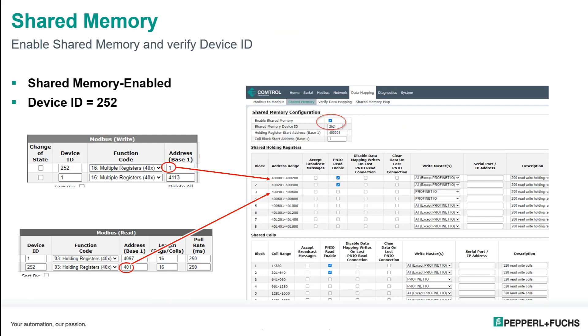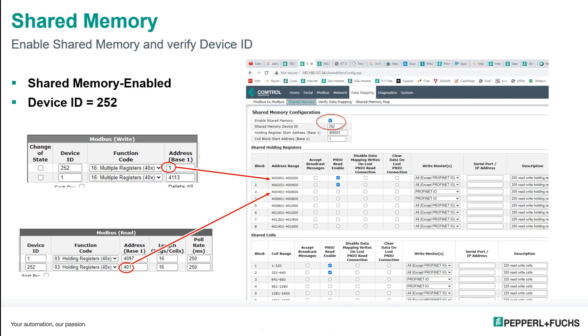Next thing, shared memory. We want to make sure that this is set up correctly so we can see it in the Siemens PLC. So go to the Shared Memory tab under Data Mapping and double-check that the address is 252, just like I said the default was, and make sure the Shared Memory checkbox is selected. Choose Save.